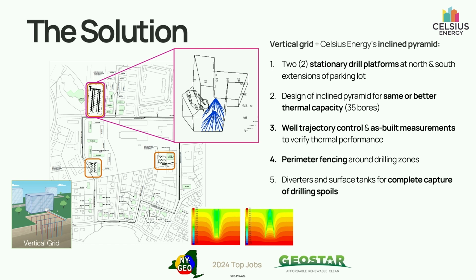The focus on our inclined pyramid solution, which is a unique Celsius Energy delivery, was on that north platform, north parking lot. Here we installed 2 stationary drill platforms - critically important. One at the northernmost extent of the parking lot, one at the southernmost extent. The rig sits and operates for a 14 to 16 week period in and amongst that individualized platform, drilling a number of inclined bores out in all directions, but staying isolated in that one spot - not having to lift, shift, and mobilize 25 feet every 3rd day throughout the execution of that drilling.